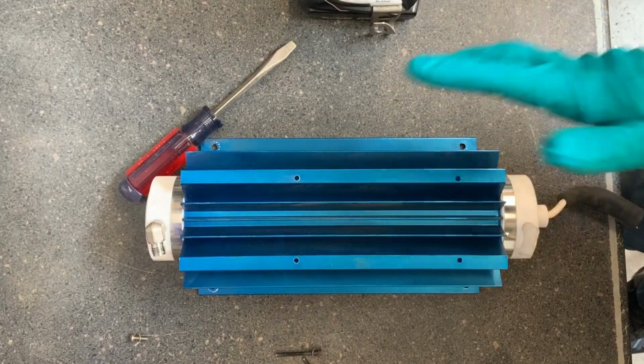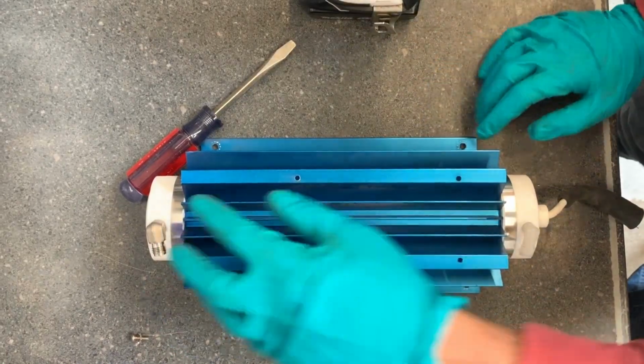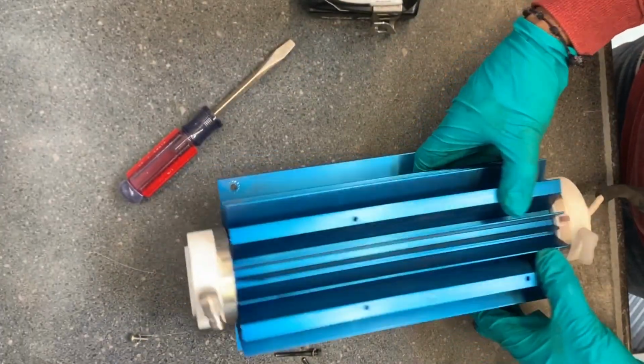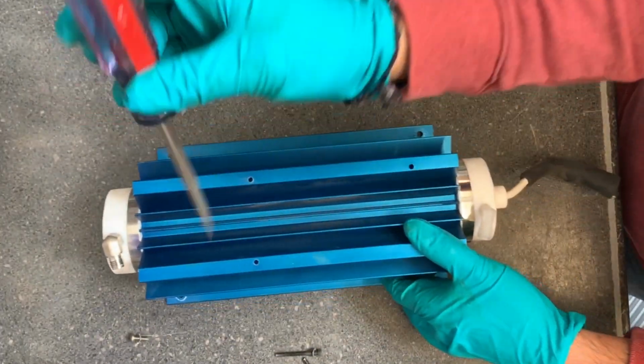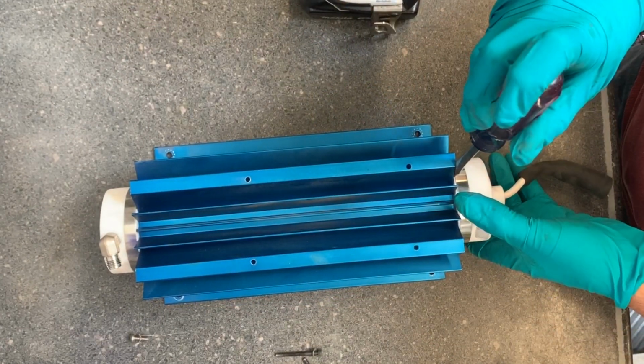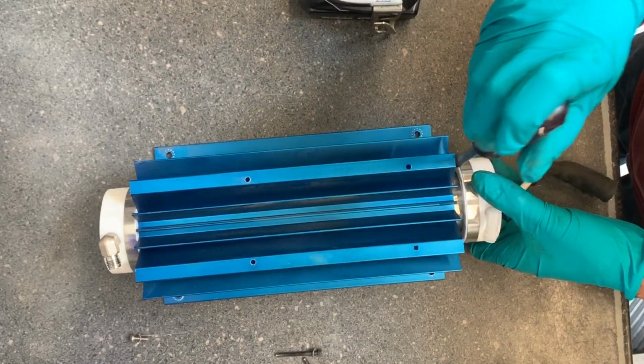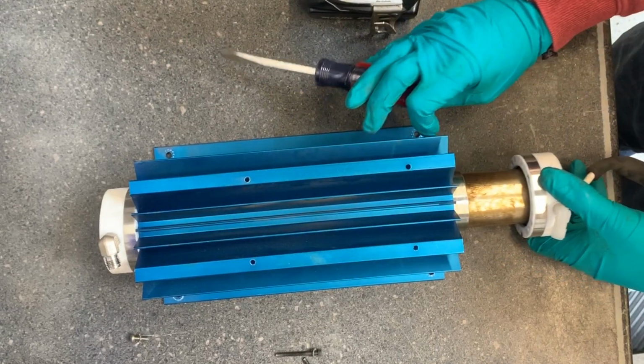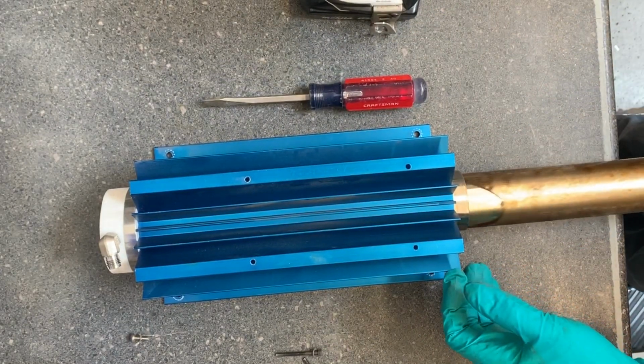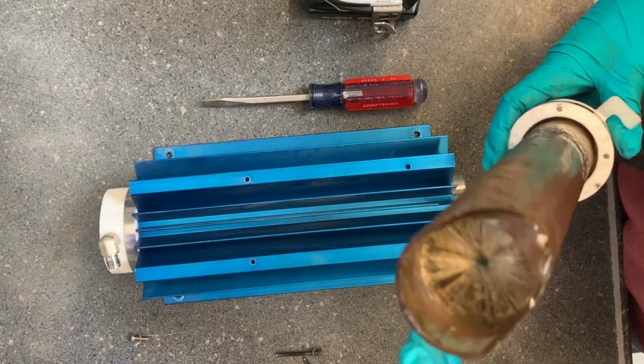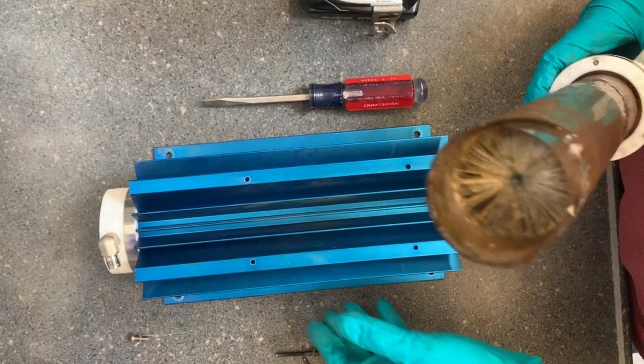So I'm going to be showing you how to rebuild your chamber. You want to remove all 4 screws from each end cap. You want to get a flathead screwdriver and just push the end cap out slowly without trying to break the glass. You pull out. This one has broken glass in it, so that's definitely going to give you that red fault light.